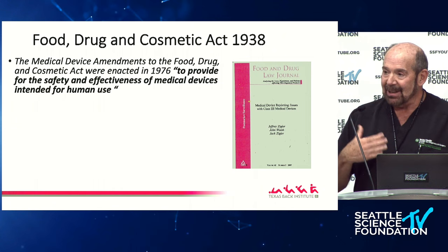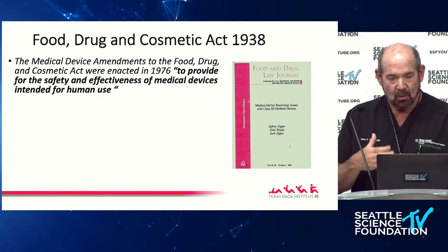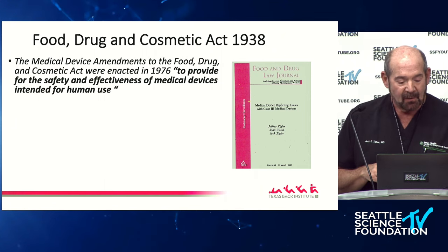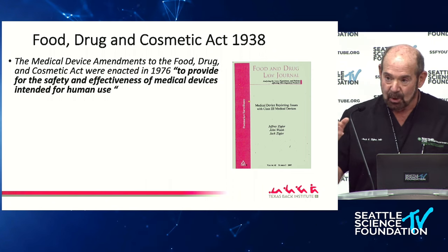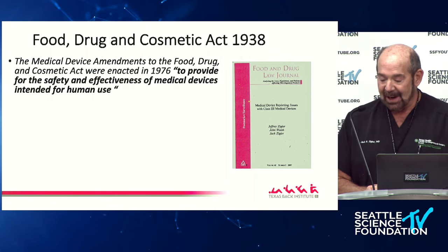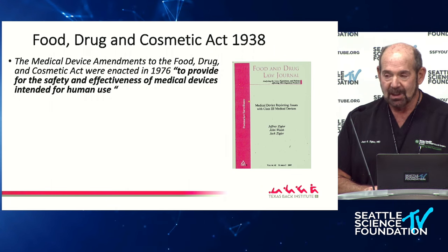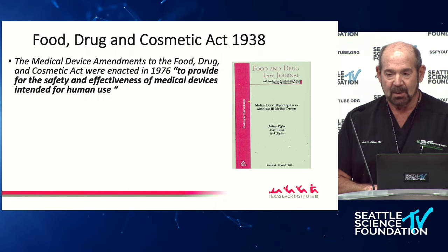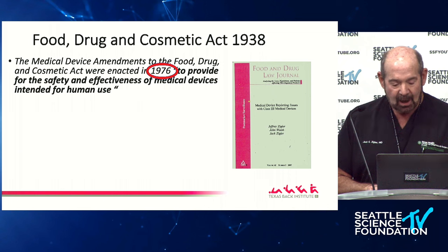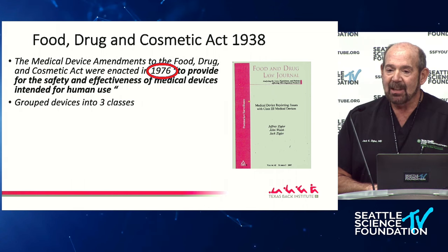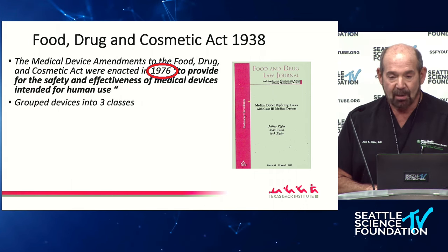Again, it was a mandate from Congress to the FDA, to provide for the safety and effectiveness - that's where those two words came in - of medical devices intended for human use. That was the first time medical devices were specifically put under the purview of that agency. And they grouped devices into three different classes.